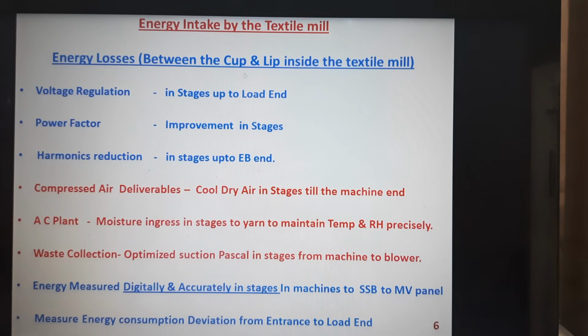In general, the energy intake for the given textile mill, the energy losses happening between the cup and the lip inside the textile mill. The voltage regulation means all the EB related transformers, they are all rated for 11 kV or 22 kV or 433 only. But the mill needs only 390 to 400 volts only, let us say around 400 volts. So in stages, voltage regulation needs to be done. OLTC has to function in some of the areas, the servo stabilizer has to function in some of the areas, some of the equipments I am trying to say, the voltage regulation is very much needed in each and every department of the mill. Then the power factor improvement.